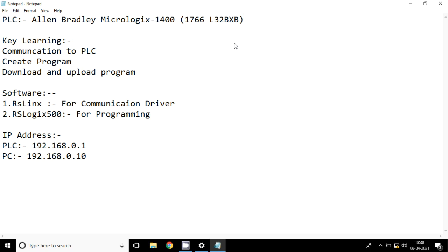First of all we need to check the IP address of the PLC. In the last video I showed how to check the IP address of the PLC and how to change it, and then we need to set the IP address of the PC. For me, the IP address of the PLC is 192.168.0.1, and the PC IP address should be in the series of 192.168.0. You can put any number in the last octet.